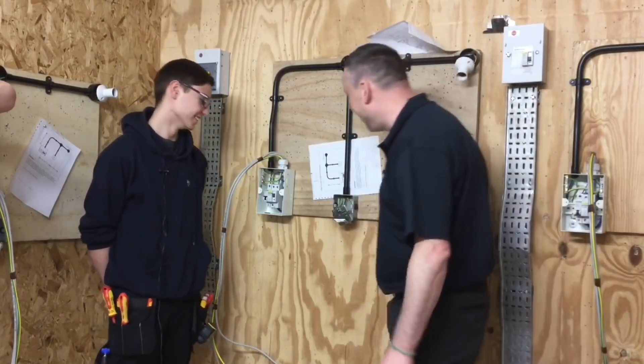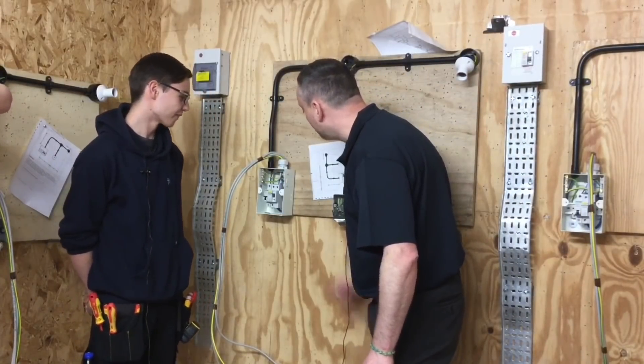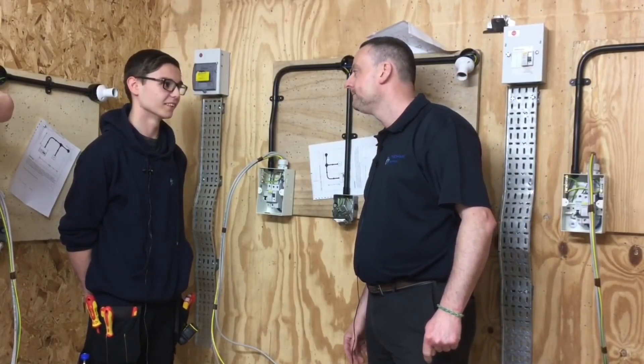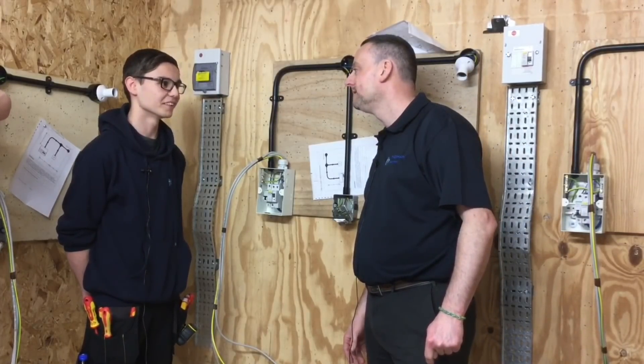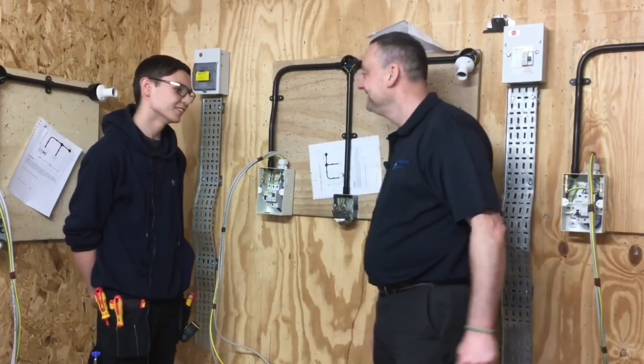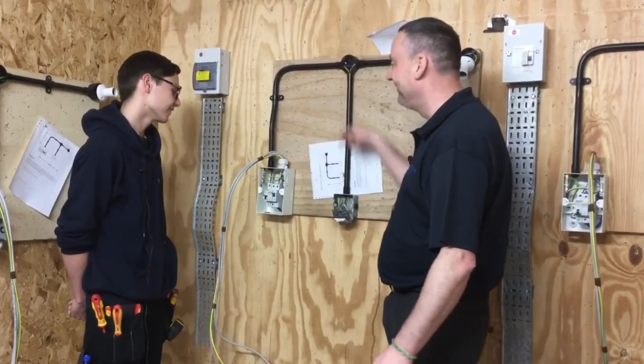What else are we going to go for? Size of cable. Why? The lighting circuit was in conduit — which size cable do we use? 1.0mm cable for the lighting circuit, yeah, all around in 1.0mm cable.